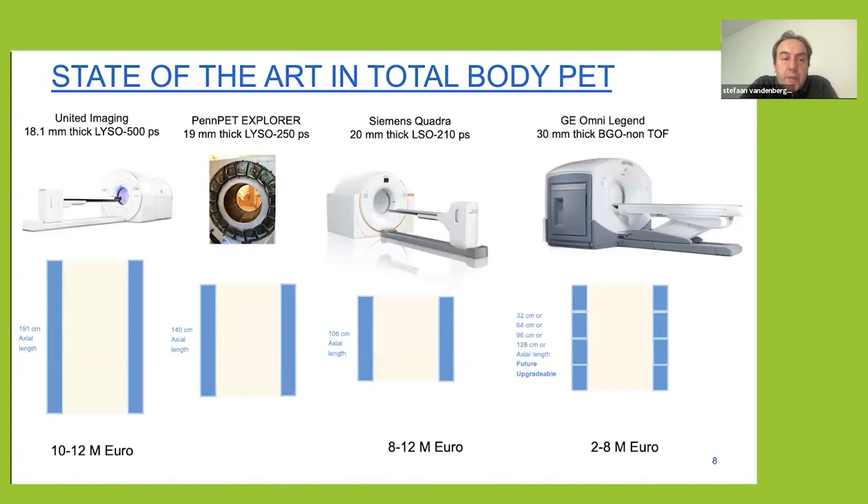The first system to come on the market was from United Imaging, a Chinese company, coming from the NIH project with UC Davis. It has a very long axial field of view — 191 centimeters, as long as most patients — but it's also quite expensive at 10 to 12 million euros. There's also a system at the University of Pennsylvania based on Philips technology, but it has not been commercialized. The system you'll find most in Europe is the Siemens Quadra, with a 106-centimeter axial field of view. More recently, GE also brought a total body PET platform to market, currently 32 centimeters but extendable to 64 or 128 centimeters, and it uses a less expensive scintillator — BGO rather than LYSO.